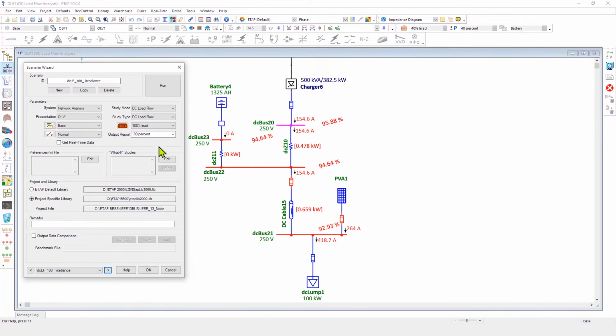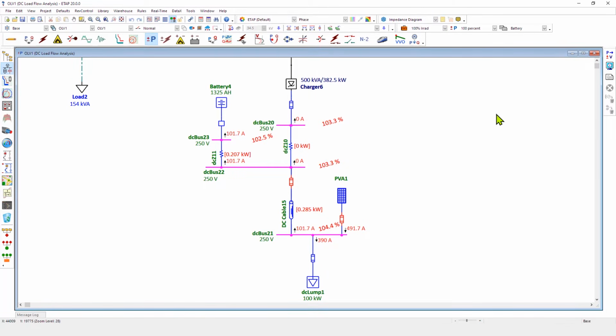And finally, once we reach 100% irradiance in our system, and let's say that's in the afternoon, the PV array is generating the majority of the power. The voltages are higher than the nominal values, and we can see that the battery is actually charging and absorbing the power, and there is no contribution coming from the battery rectifier. So once again, in summary, we can observe the behavior of the PV array, the battery, and the rectifier based on different irradiance levels of the PV panel and how they affect each other as you go from 10% to 40% to 100% irradiance. Next, let's go ahead and run DC short circuit.